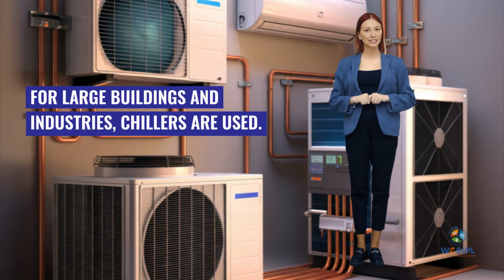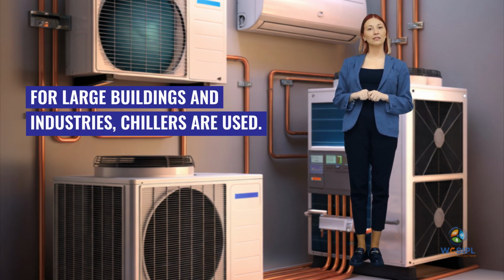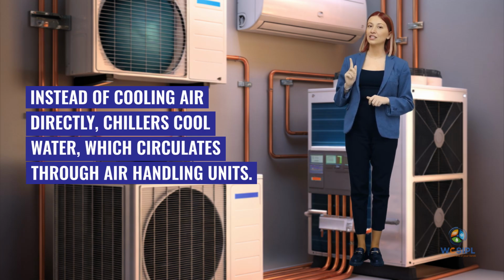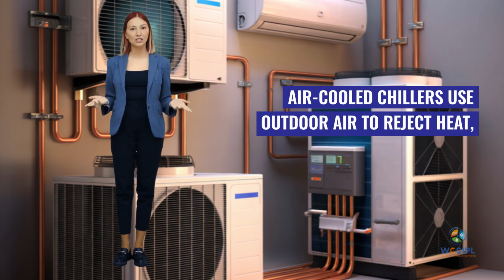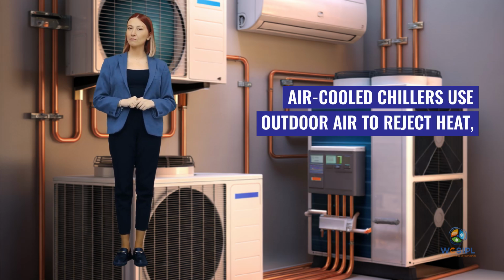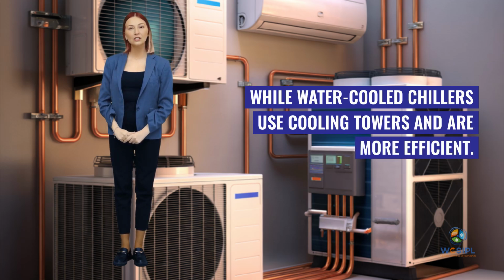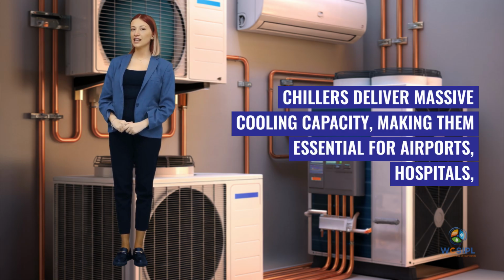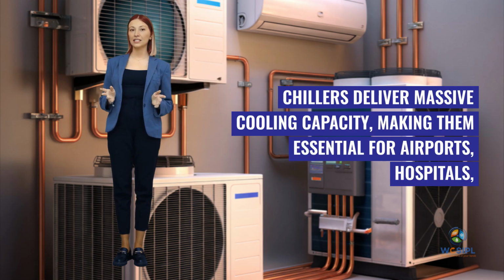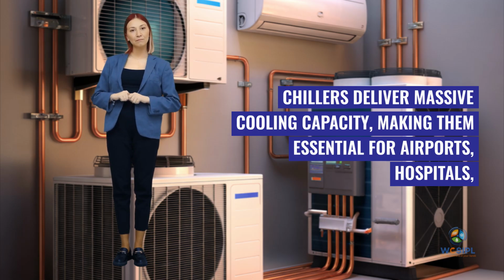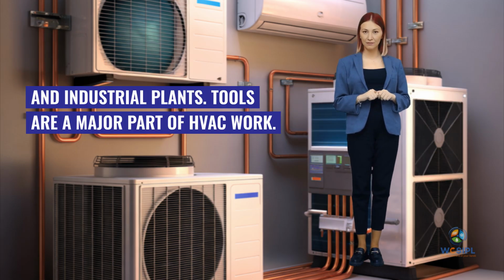For large buildings and industries, chillers are used. Instead of cooling air directly, chillers cool water, which circulates through air handling units. Air-cooled chillers use outdoor air to reject heat, while water-cooled chillers use cooling towers and are more efficient. Chillers deliver massive cooling capacity, making them essential for airports, hospitals, and industrial plants.